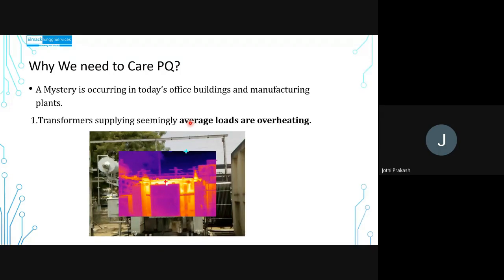So they don't know why it is heating. This is a major mystery, which led us to think about power quality healthiness. We know that a transformer has its own rating. So when we are loading the transformer at average or lesser than the rated capacity, definitely it should not heat over its rated temperature.